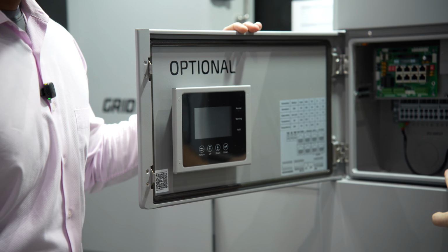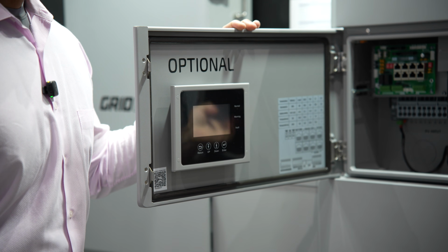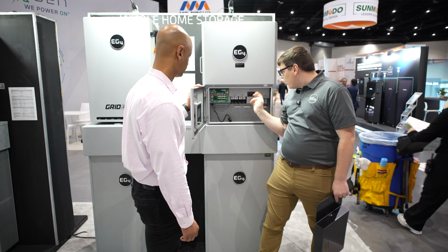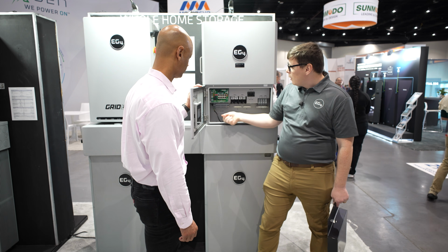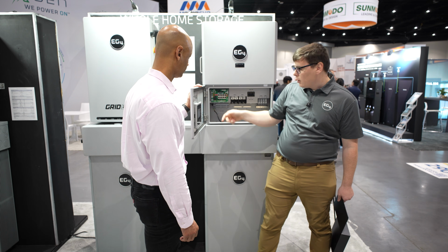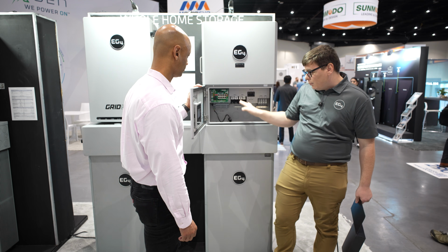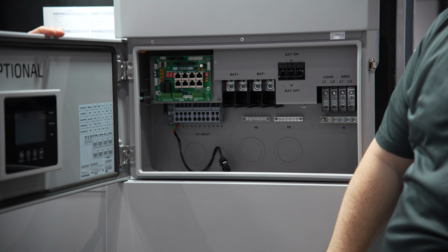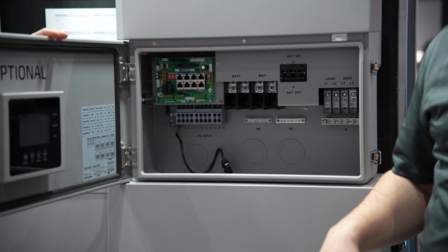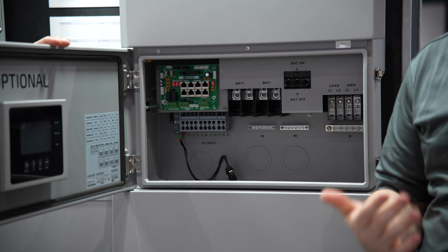And really that's about it. It's a single wire connection, one run of wire to the GridBoss, a communications cable to the GridBoss, battery communications go in here, and then the 250 amp cables from the battery come straight off the battery quick connects and into the inverter. So it's a system that puts itself together really easily.